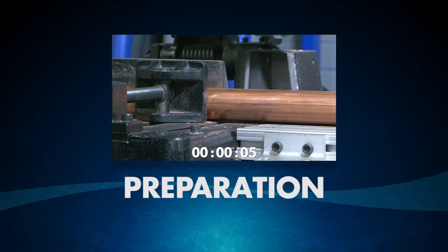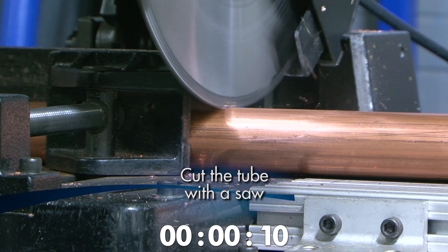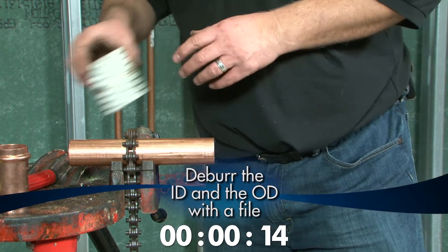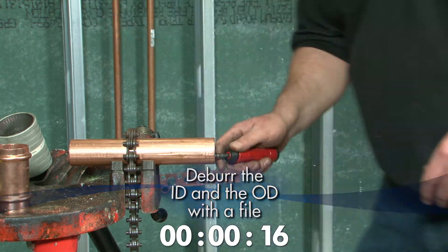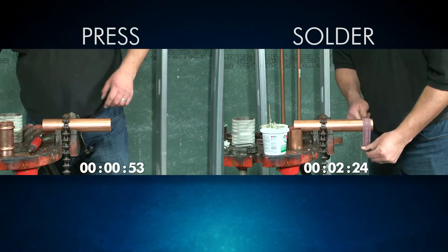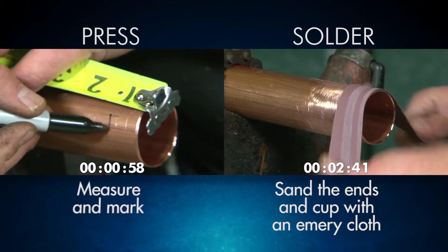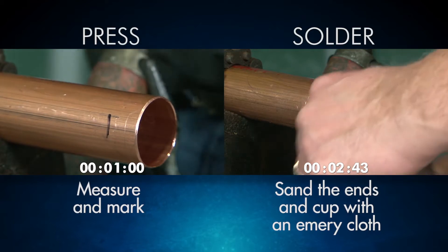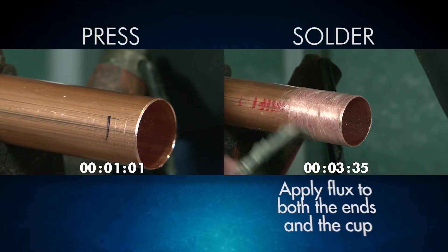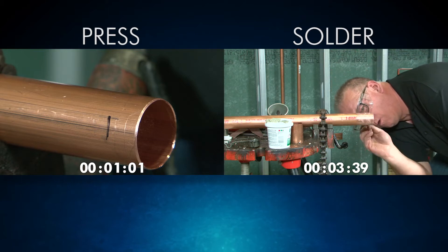Preparing the tube begins similarly in both press and solder installations. In both cases, you will cut the tube with a saw. Deburring is an important step with both press and solder installations, but more care and attention is required for press. With solder installations, you will need to sand the ends and cup with an emery cloth, while press only requires you to measure and mark the tube. You'll also need to apply flux for solder installations. With press, however, your prep work is done, saving you valuable time.